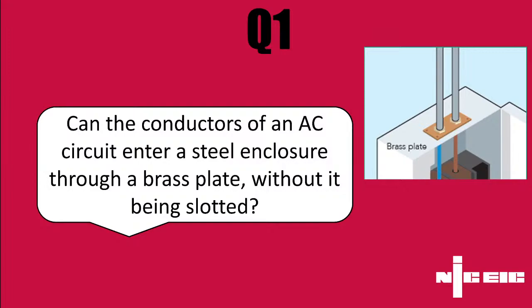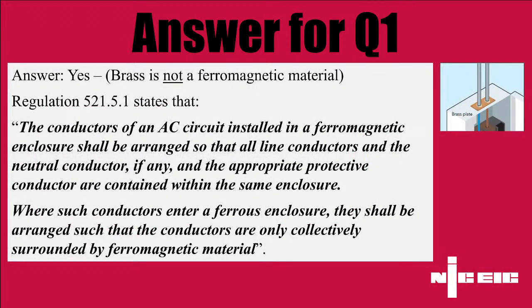No, we don't. To be fair, brass is not a ferromagnetic material, and you often see brass and other non-ferromagnetic materials, such as different grades of aluminium or Paxolin, or toughened plastic as well. You often find it when you've got larger single pole conductors from a generator enclosure, for example, where you have these other non-ferromagnetic materials to mitigate the effects of what we know as eddy currents or ferromagnetic effects. You can use brass, it is absolutely fine.